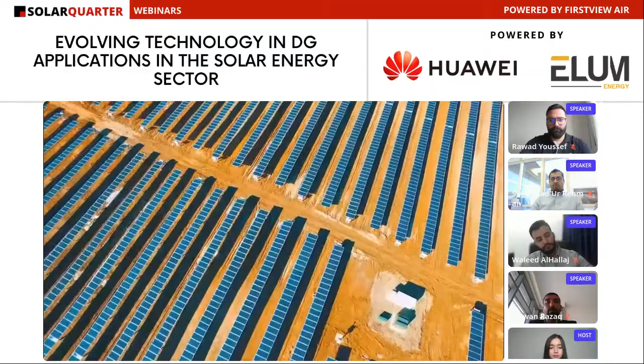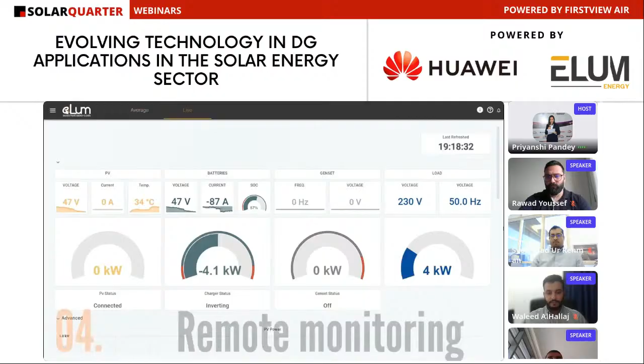The Elum HFS controller is compatible with all the main brands of solar inverters on the market through RS485 Modbus or Modbus TCP, and also with on-site genset controllers, meters, or third-party sensors. It is fully autonomous, and its local intelligence allows it to store data and operate the plant in case of internet loss. When the HFS controller is connected to the ePower Monitor web platform, site operators can remotely visualize all plant data, like power production and consumption, and oversee the site operating status through logs and alarms from the diverse material on site. The ePower Control Hybrid Fuel Saver controller has already been implemented in more than 15 countries worldwide, such as South Africa, Lebanon, and Madagascar.